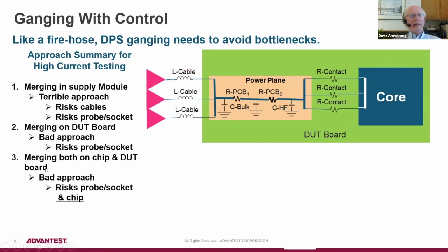I put this third option on here and actually got pushed back internally. This, in my opinion, is by far the worst case scenario, because if you have a power rail on your device and on your DUT board and you have a contact problem, your current flow will flow through the contacts that are still there and come down on your core or device to where it's needed. As a result, you'd have too high a current on the die, on the power rail, and could actually have electromigration in addition to blowing up your part. So that's a bad thing to do.